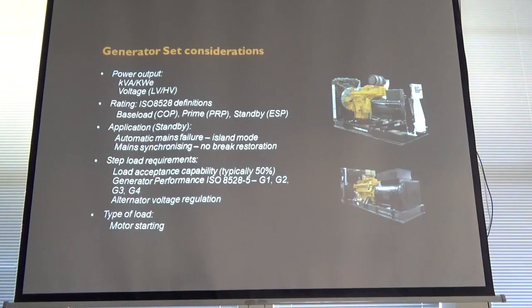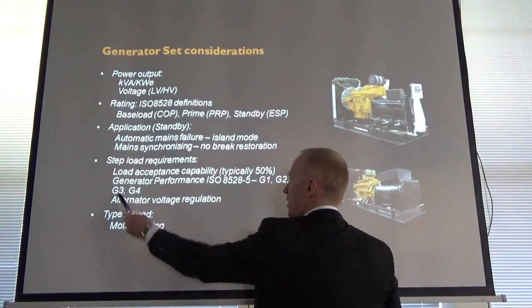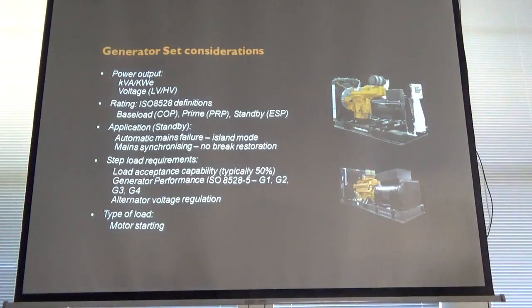But the implications: if your load is, say, a 500 kilowatt unit, and you tell me G3, what that essentially means is a bigger alternator, probably a bigger engine, to keep the load step within that tighter tolerance. And that's the key thing. So you can see how they are. Often you'll get customers and consultants saying they want G3. Well, they're only starting pumps and general systems. It's completely over the top. And obviously you need to make them aware of that, to see whether they really want that and what the implication is if that is the case.